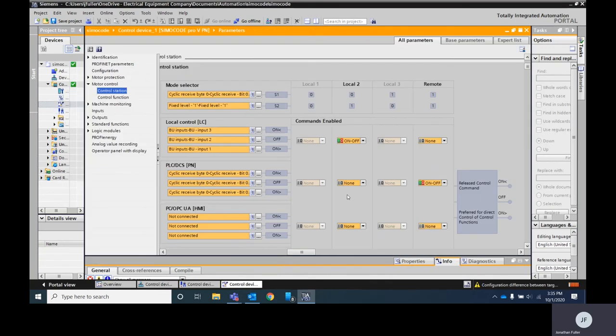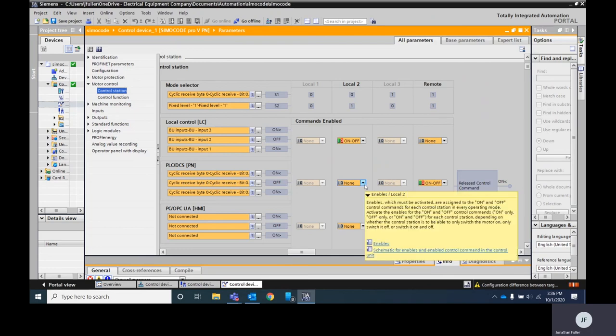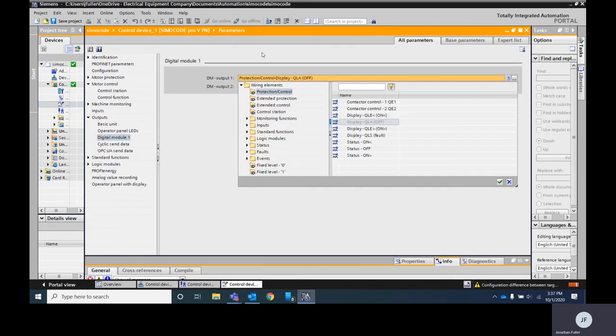One last thing I can do: I can go over to the commissioning of my device and I can click on this motor control and control station. In here I've got kind of a truth table and I can go in here and set whether I can use hardwired push buttons or the actual buttons on my control module, my HMI device, to see what takes command of the device and what takes higher priority. By going in and changing some of these I can make those changes so I can make it local or remote or remote only or local only.